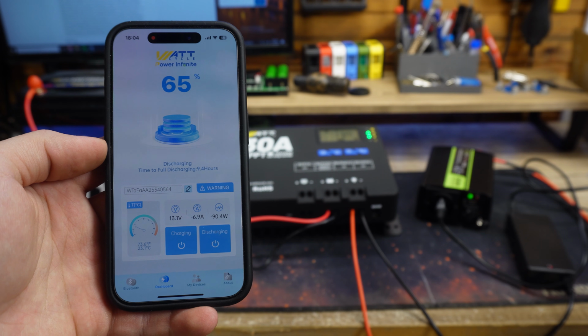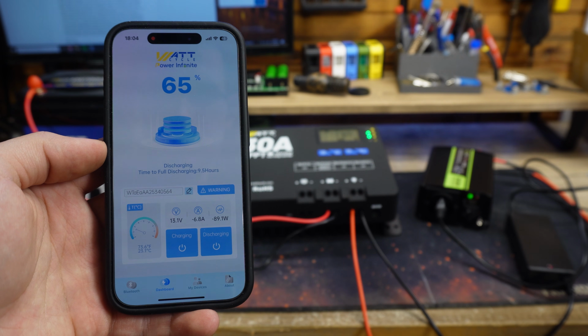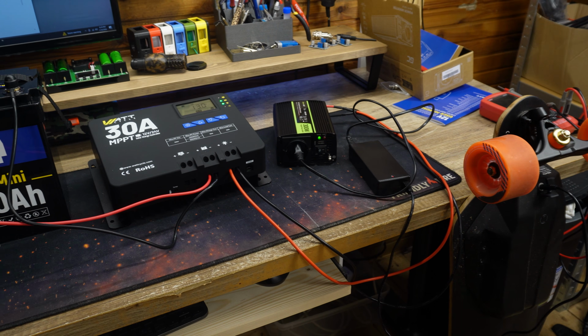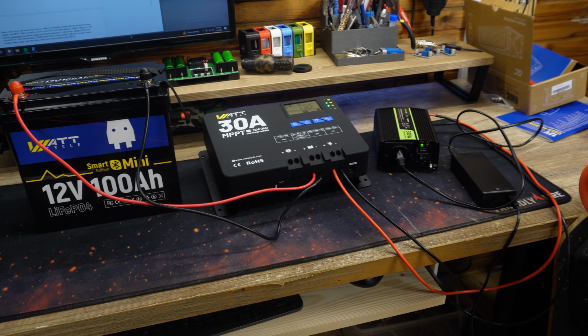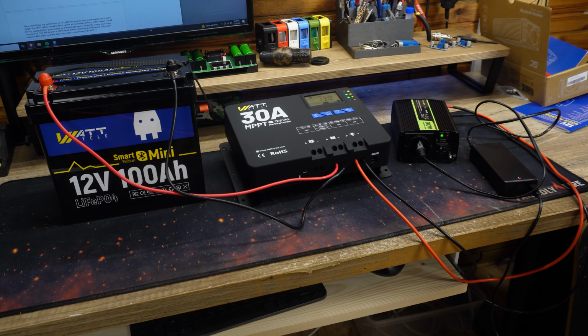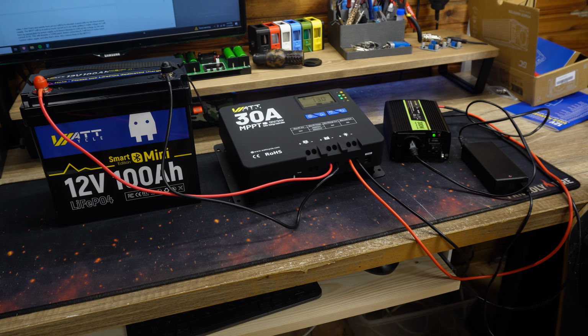Now I see that we also get an estimated remaining operating time, which is really cool. The downside of the system is that the BMS cannot reliably detect lower currents, which means that the battery percentage won't be precise if you have tiny loads connected.